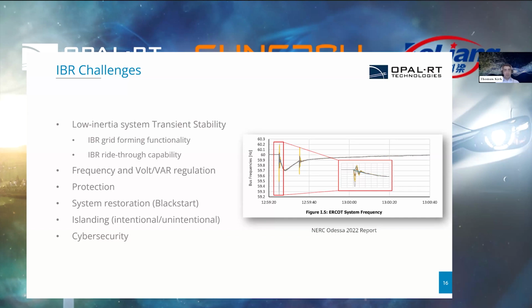How IBRs are used as grid forming devices, their ride-through capability, the configuration of that is crucial. There's going to be challenges associated to the frequency and volt-var regulation, protection schemes, because of where they are placed in the circuits, old protection schemes are not necessarily going to be applicable to the new grid, so those techniques are being revised. There's some really good articles already on that topic.